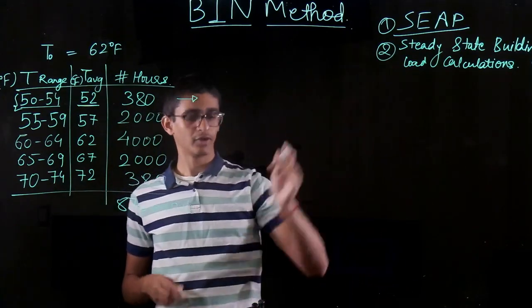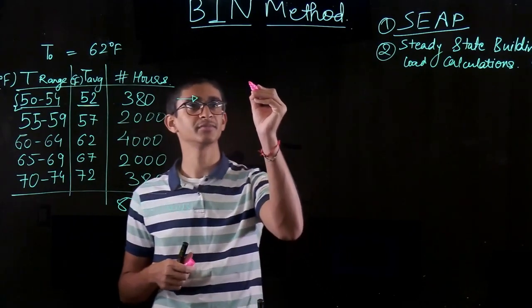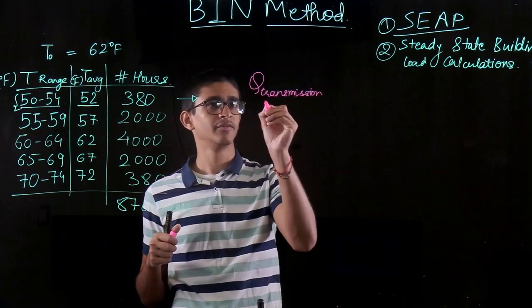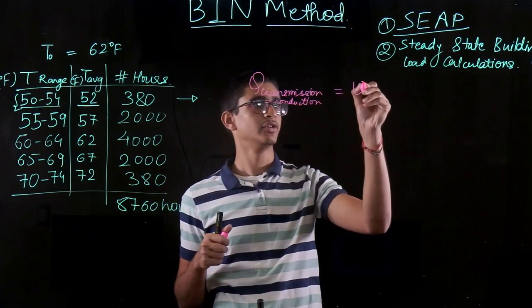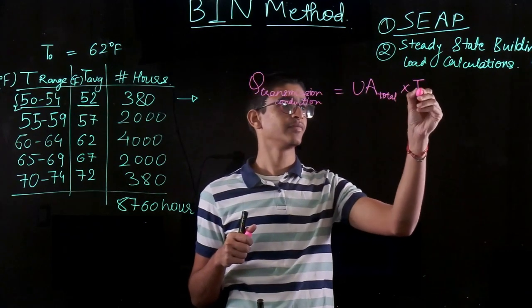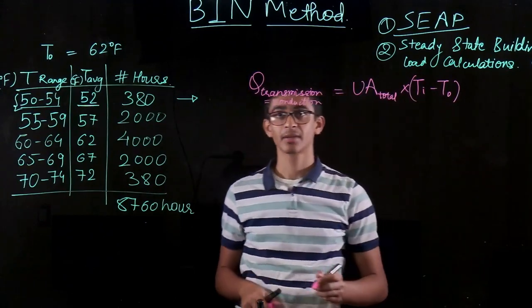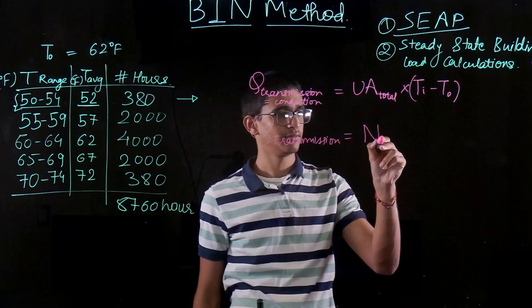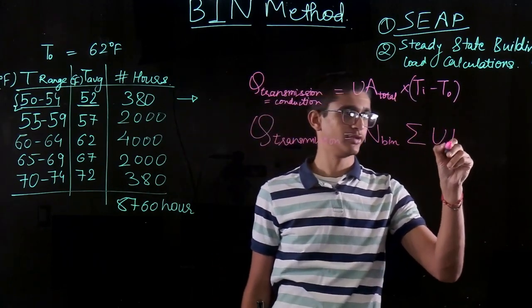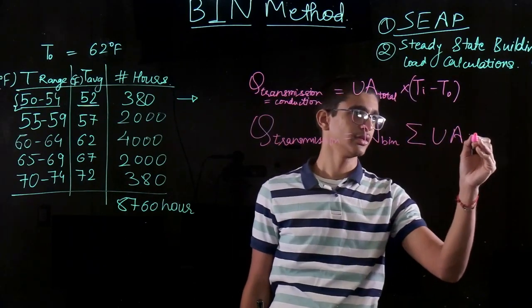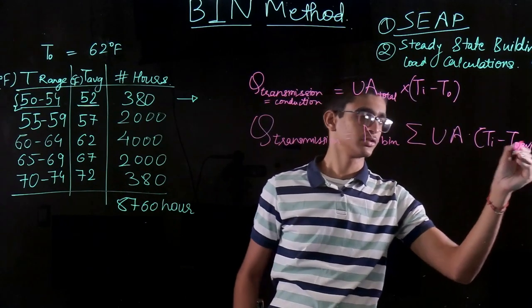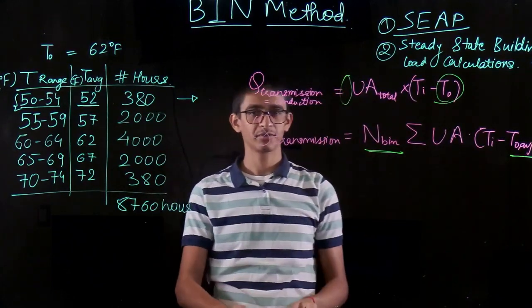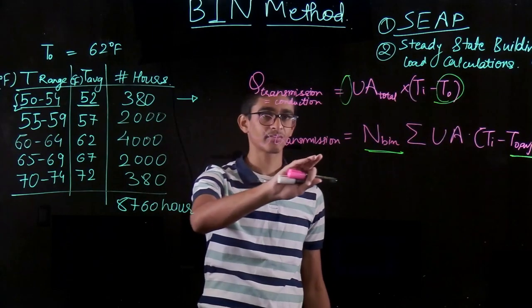The difference in the formula is straightforward. Earlier in steady-state building load calculations, the transmission load due to conduction was: Q = UA_total × (T_in − T_out), where these were average temperatures. But now, in the BIN method, the formula becomes Q_bin = N_bin × UA_total × (T_in − T_out_average), where N_bin is the number of hours in that bin. The key difference is we are taking into account Q for each bin separately using its average outdoor temperature. For each of these bins we separately calculate Q_transmission and add them up, which gives a better overall estimate.